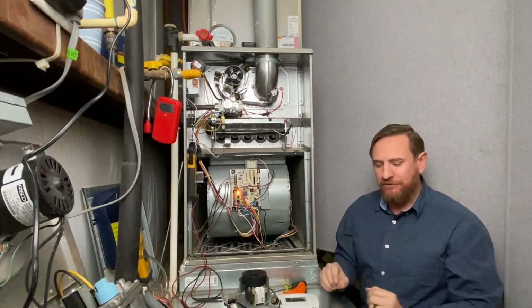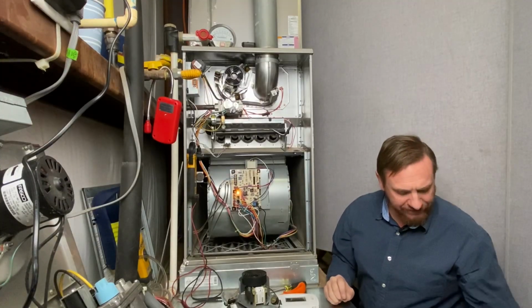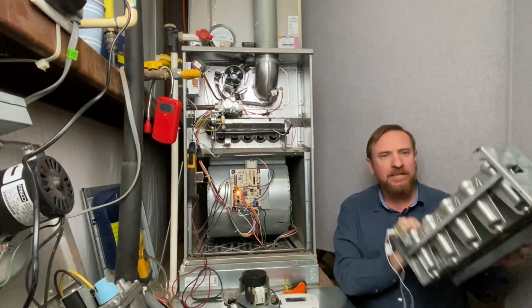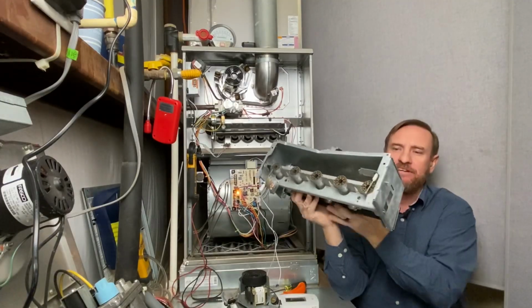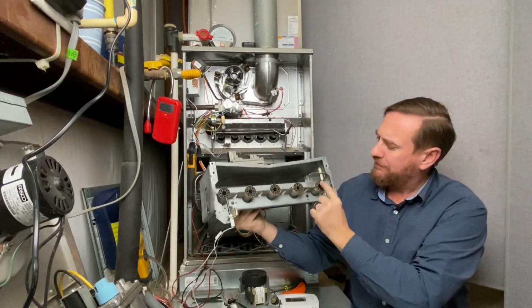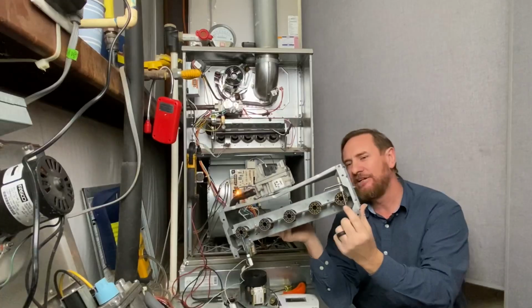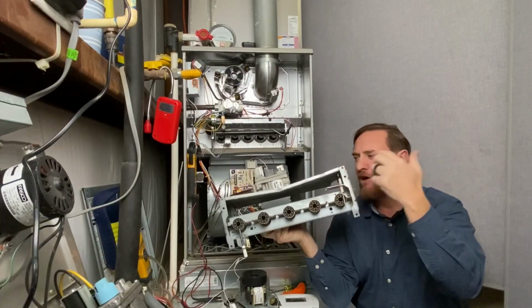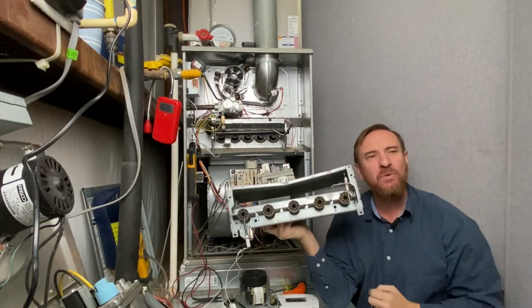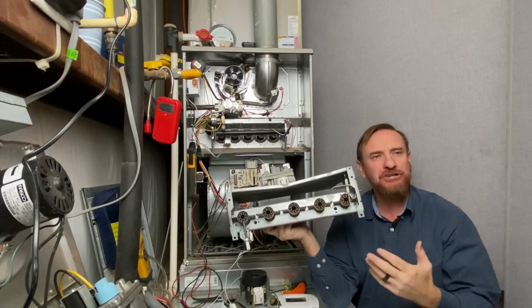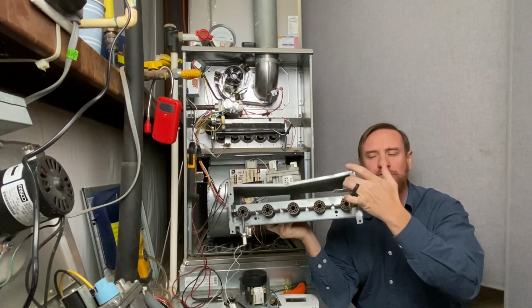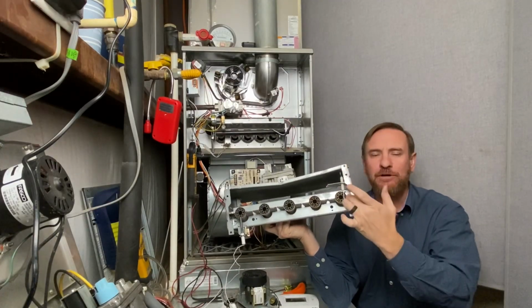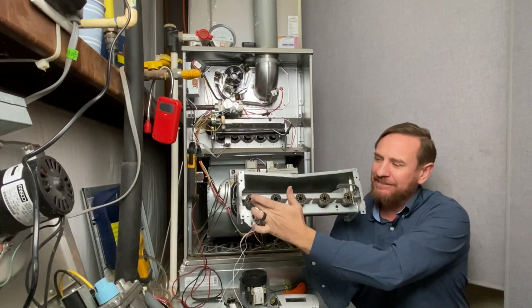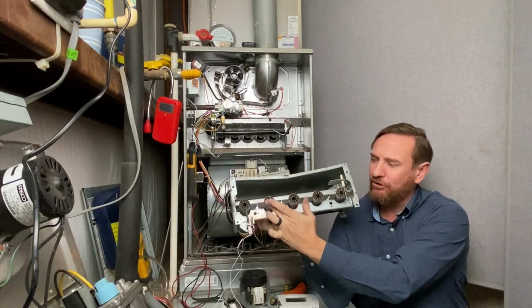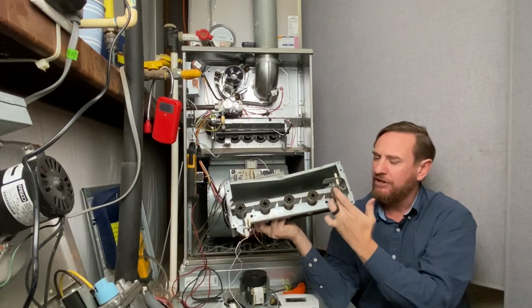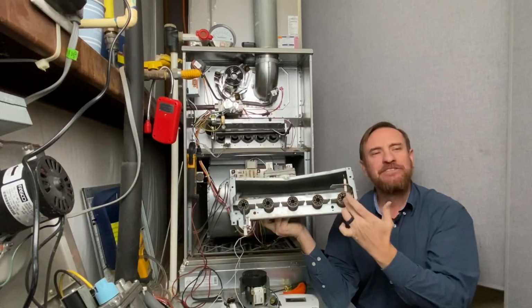Now, we only have a few seconds to prove a flame with a process called flame rectification. So here I've taken the burners out, and we have over here a single rod. And this single rod will only have one wire to it. Almost everything has at least two wires to it to open and close, measuring things. But the flame sensor only has one wire going to it and one rod. Notice it's igniting the flame on one side. It carries across all these crossover valves to my flame sensor on the opposite side.